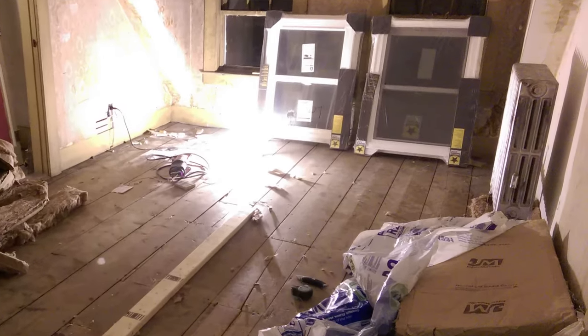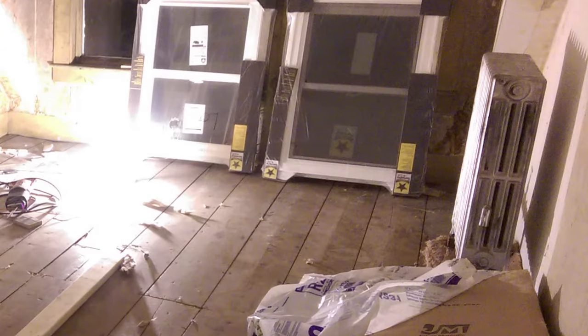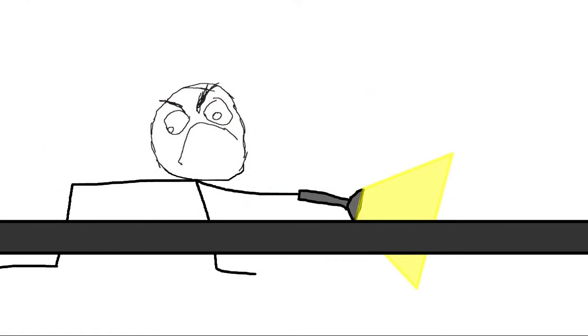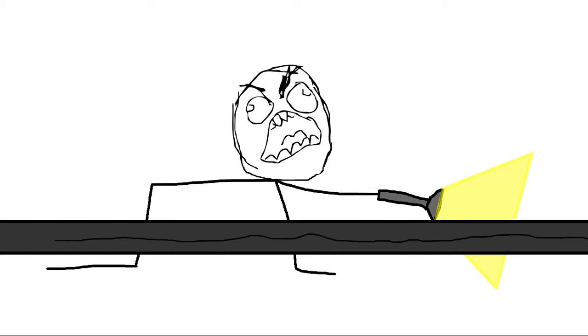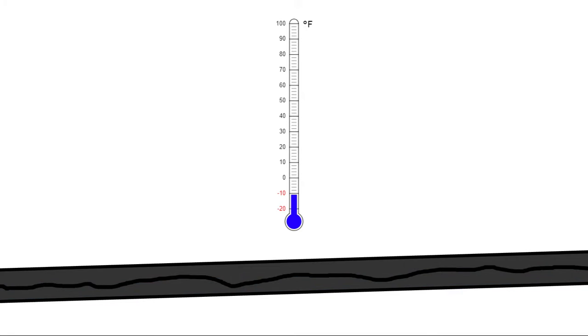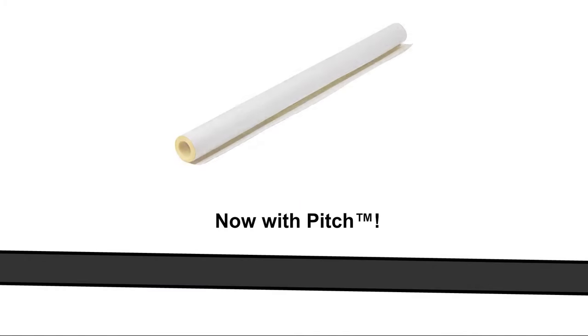Moving to the bedroom radiator, this one gave me two interesting problems. Once again, there was no heat whatsoever. Upon tracing the pipe into the wall and into a crawl space, I discovered that the cast iron pipe had actually split in half lengthwise. I suspect this was for two reasons. For one, improper pitch allowed water to pool, and two, because this was uninsulated in a crawl space, the trapped water froze and split the pipe. So I replaced that section of pipe and wrapped it in fiberglass.